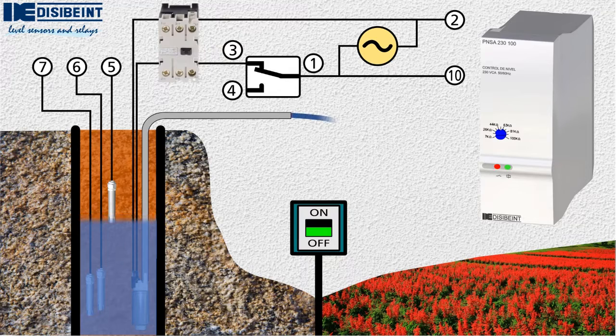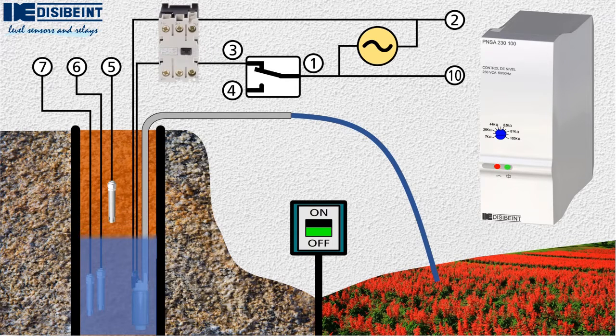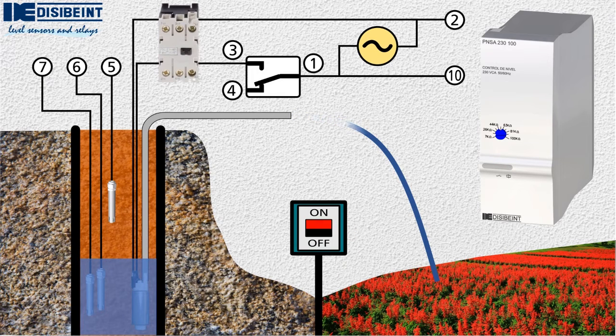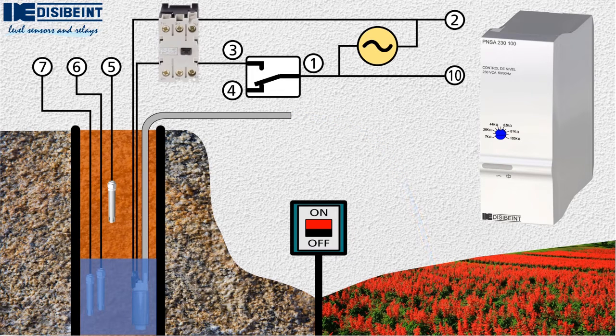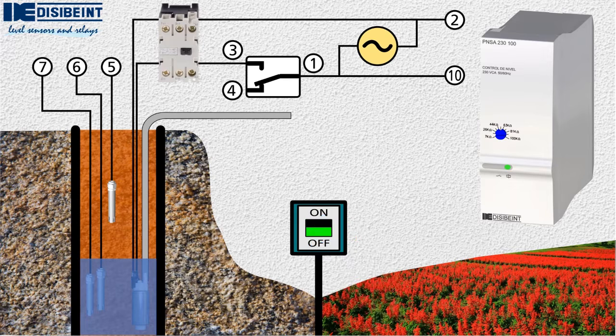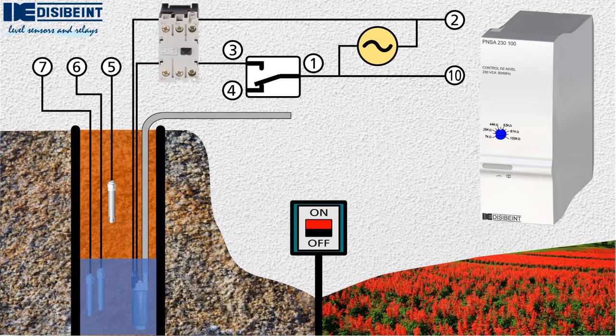By stopping the system manually, we restore the conditions of the PNSA level relay, waiting for a new startup. In this case, if the water level is between the maximum and minimum probes, the pump will not start until the water reaches the point where the maximum probe is located.